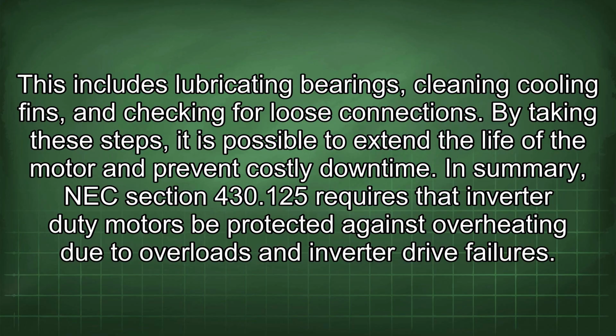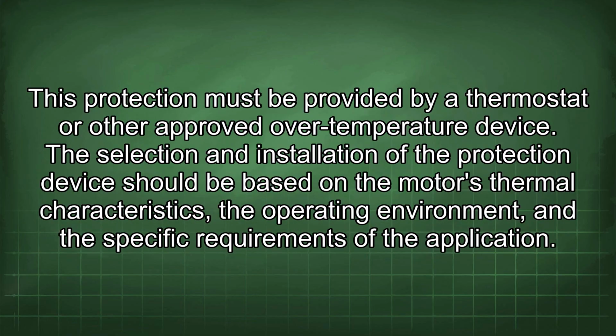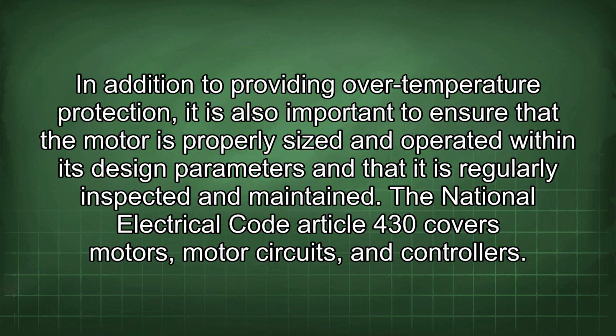In summary, NEC Section 430.125 requires that inverter duty motors be protected against overheating due to overloads and inverter drive failures. This protection must be provided by a thermostat or other approved over-temperature device. The selection and installation of the protection device should be based on the motor's thermal characteristics, the operating environment, and the specific requirements of the application. In addition to providing over-temperature protection, it is also important to ensure that the motor is properly sized and operated within its design parameters and that it is regularly inspected and maintained.